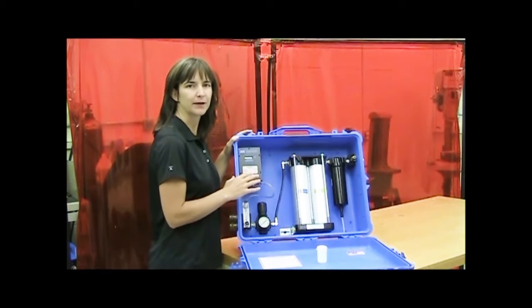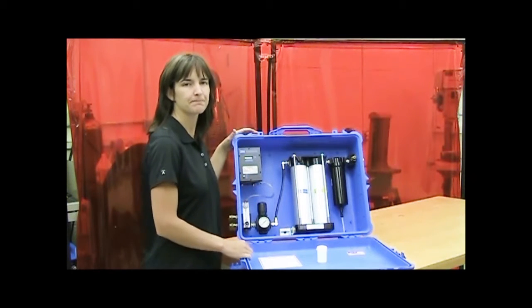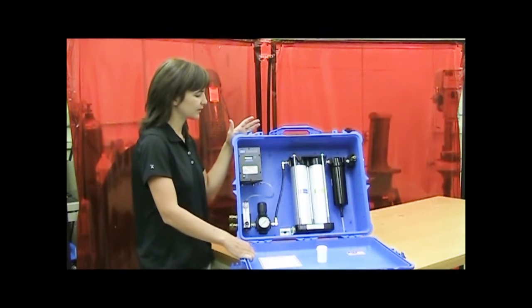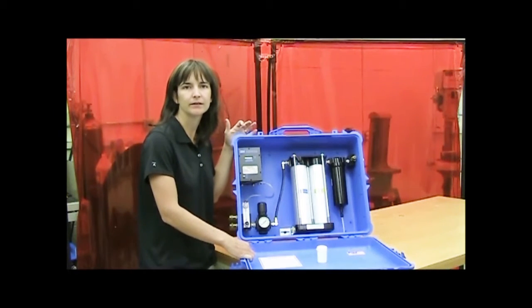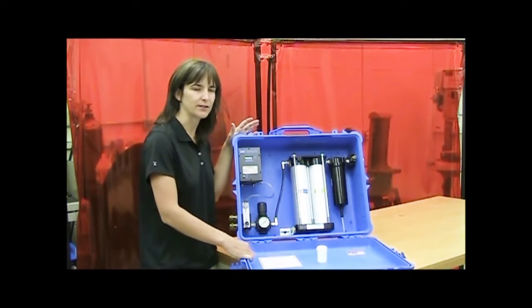Itself is the same in all of the 3M panels, so the process of changing the sensor is going to be the same as well. So why would you change the sensor in your monitor? Essentially, if you're having trouble calibrating the monitor, it's a good possibility that your sensor is bad.